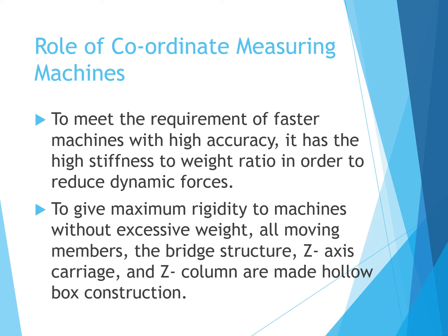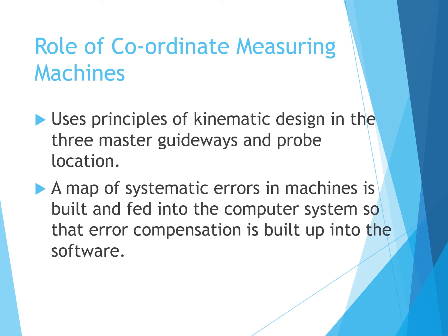That is, in the Z axis, if we have a carriage, then in the Z axis there is a column of hollow type, depending on the type of CMMs. So it is going to have high rigidity to machines. Then it uses the principles of kinematic design in the three master guideways and probe locations. So in X, Y and Z directions you have guideways.